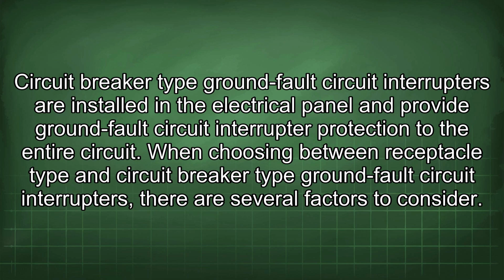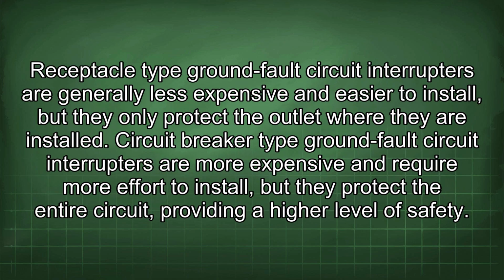When choosing between receptacle type and circuit breaker type ground fault circuit interrupters, there are several factors to consider. Receptacle type ground fault circuit interrupters are generally less expensive and easier to install, but they only protect the outlet where they are installed. Circuit breaker type ground fault circuit interrupters are more expensive and require more effort to install, but they protect the entire circuit, providing a higher level of safety.